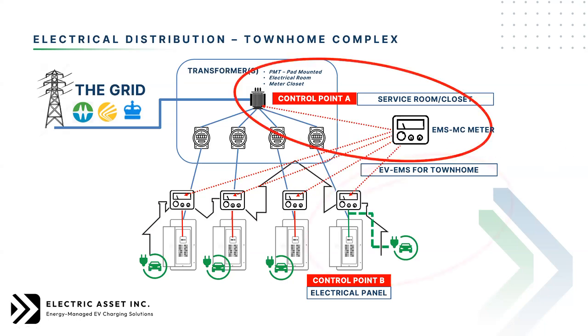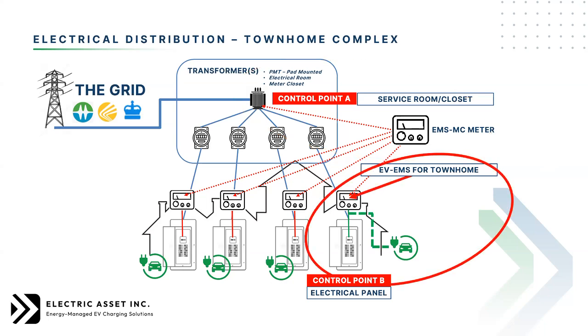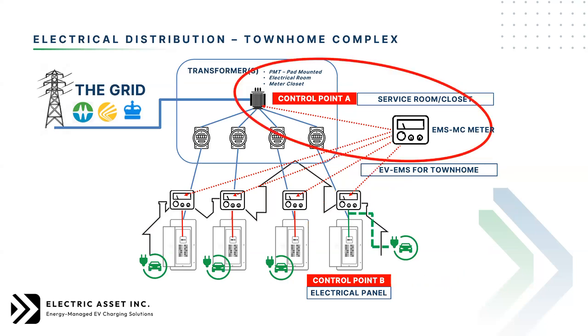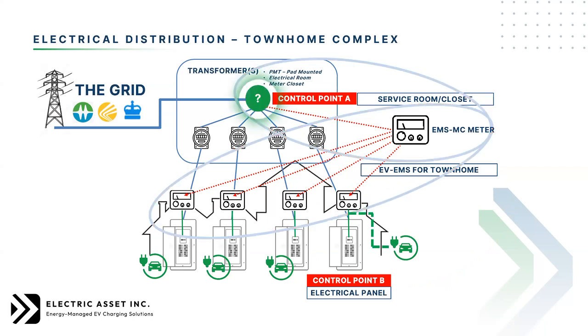So again, the EV EMS controls at the townhome level, and the EMS meter center controller controls at the panel, but it also monitors the individual townhome panels as well. Keep in mind the main safety factor is you don't want to overload the centralized power source for the cluster of townhomes.